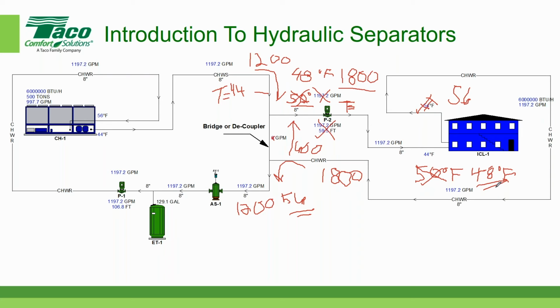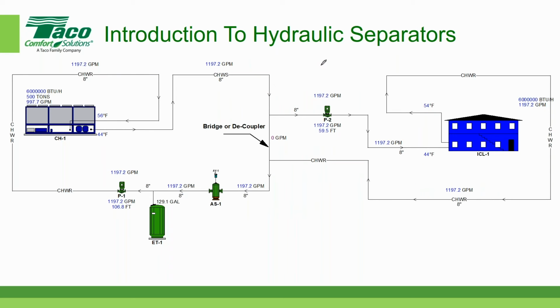So the bottom line here is that, and let me erase all this stuff. The bottom line is that when the secondary flow is greater than the primary flow, then we get a rise in temperature entering the building. And when we get a rise in temperature, we could have two issues. One, we could have a capacity issue. That remains to be seen, but we could also have a dehumidification issue. If the dehumidification characteristics were based on an entering water temperature of 44 and we now have 48, we're not going to do as much dehumidification.